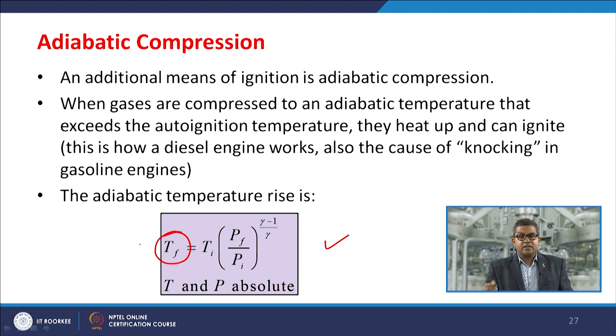So, you can calculate the adiabatic temperature by this standard thermodynamic relationship. Tf is equal to Ti into Pf upon Pi to the power gamma minus 1 upon gamma, and T and P are in absolute form. So, you can calculate, and if this temperature is just above your auto ignition temperature, then definitely you need to take certain measures to minimize the effect of auto ignition.